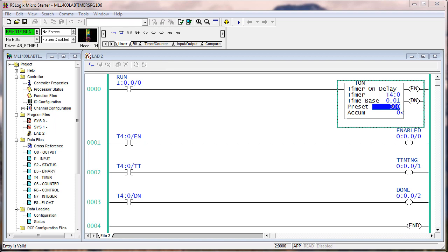In my list: rung zero goes true is number one; enable bit set is one — when the rung goes true it sets the enable bit; timer timing bit is set, labeled two or three; accumulate increments is three; accumulate equals the preset is four; done bit is set is five; and timer timing bit is cleared is five or six. It's hard to say how many of those things occur simultaneously versus with an actual scan in between. The only critical thing is that you understand the sequence of the three control bits based on the relationship of the preset and accumulate.